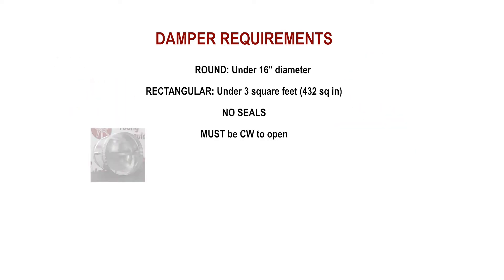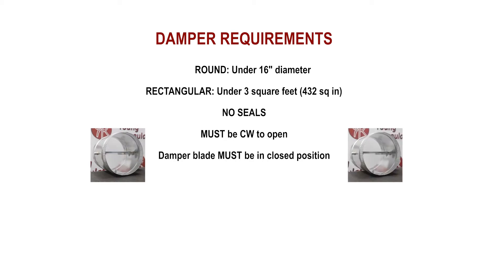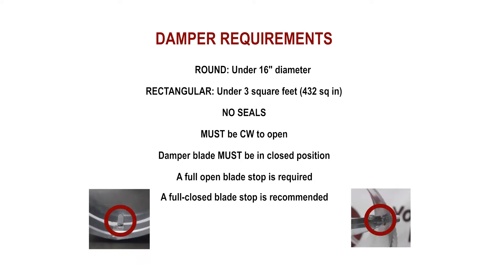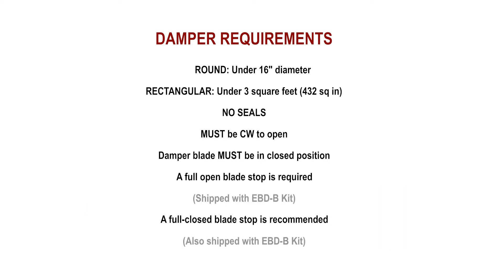The damper must be clockwise to open and must be in the full close position at the time of installation. One blade stop at the full open position is required, and one blade stop at the full close position is recommended. Both blade stops ship with the EBD-B kit.